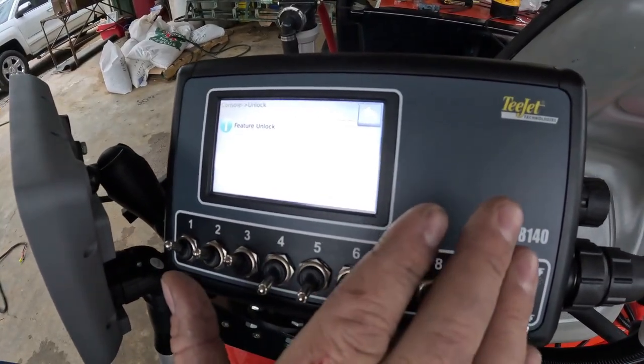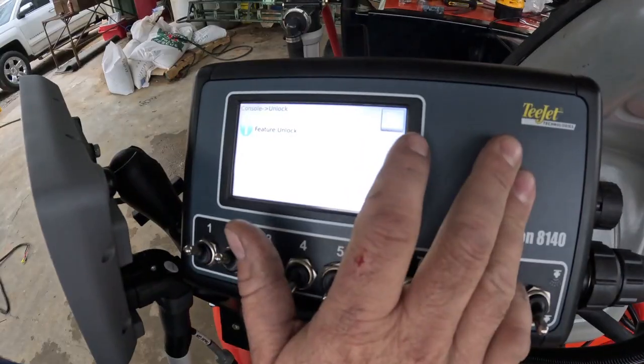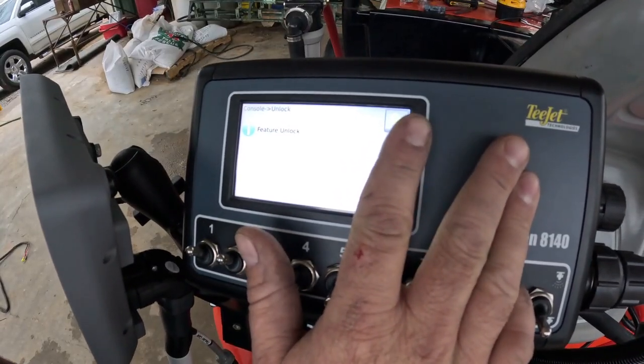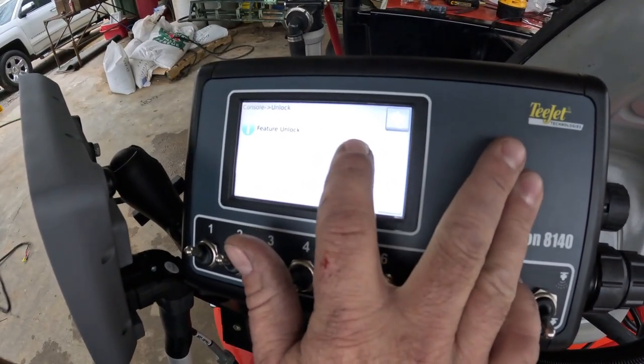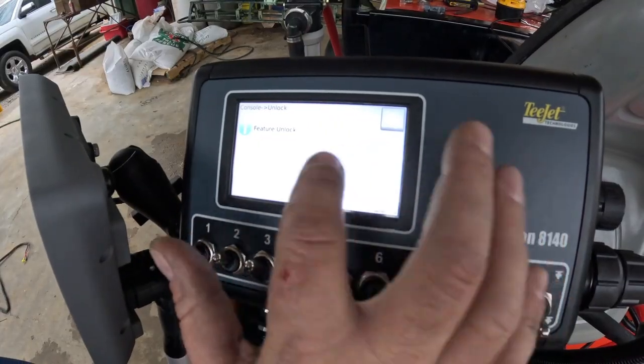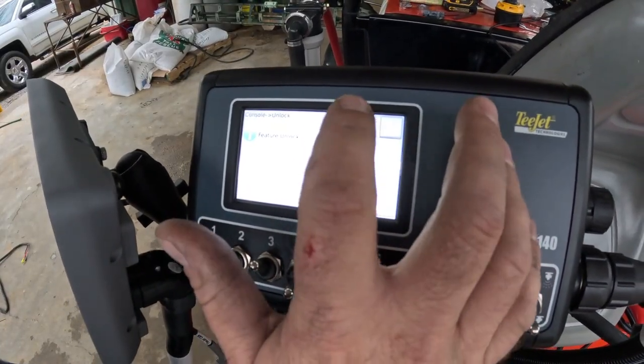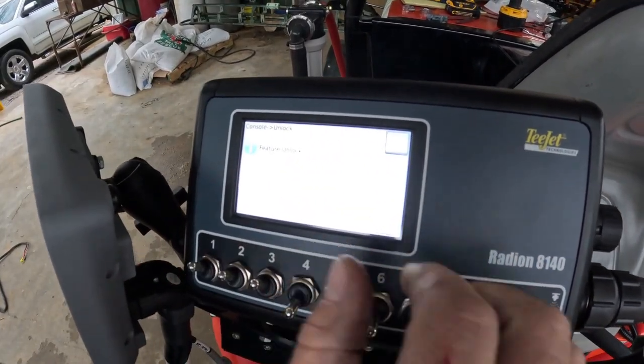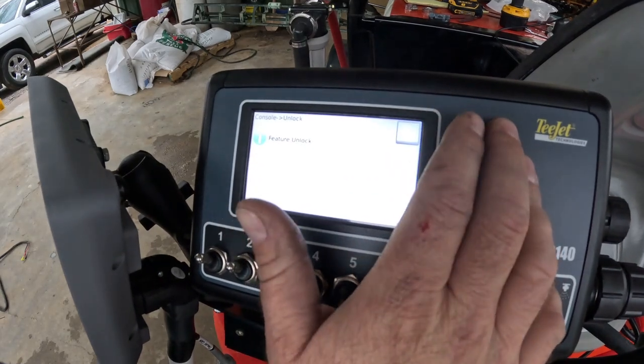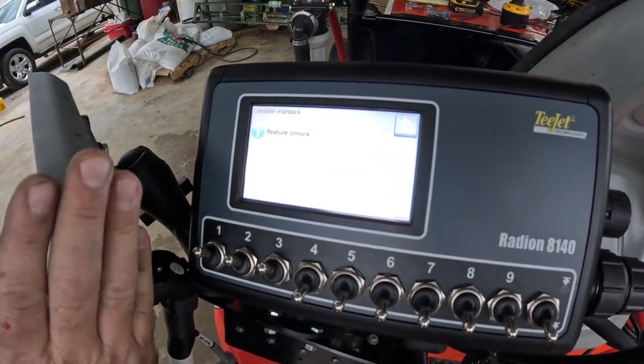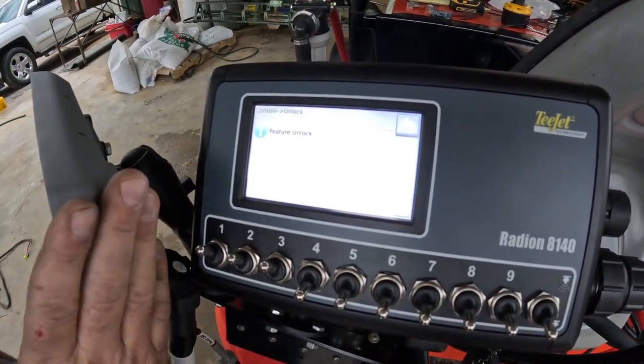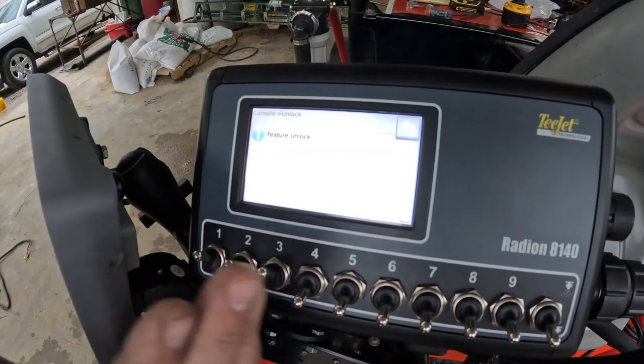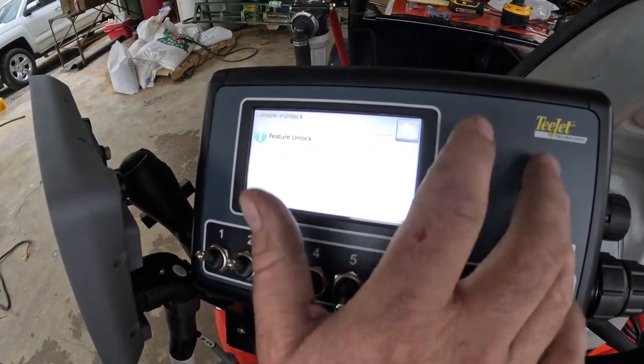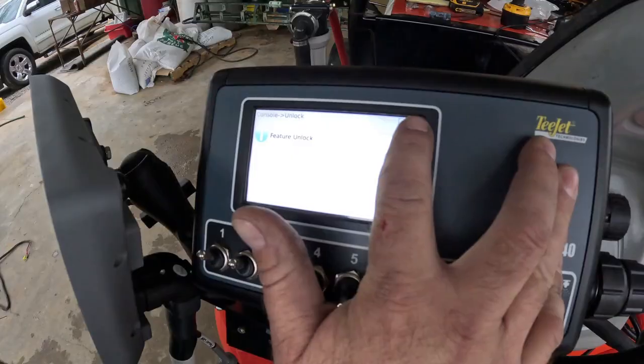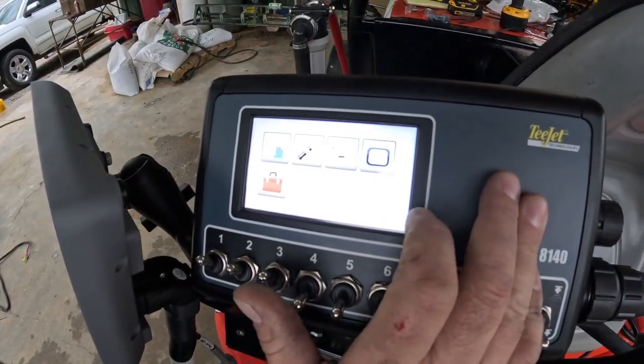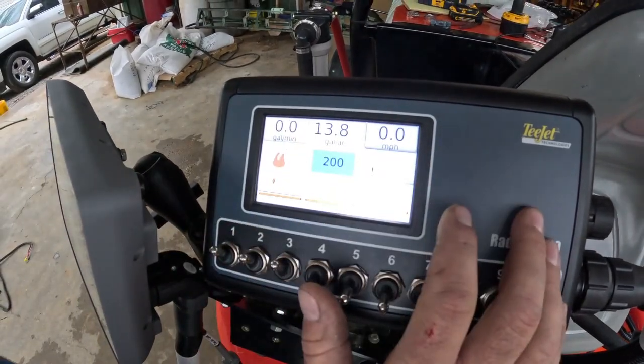If your system is not already unlocked here, there will be a sheet of paper that came in the box that gives you the unlock code for this. And of course, since it's already unlocked, it's grayed out, but then you would select it, type the code in, hit the check mark, and it would unlock it. That has to be done before it will talk to the Matrix 908 where we set up the CAN connection earlier in the Matrix 908. So now we can go back to the home, back to the working man.